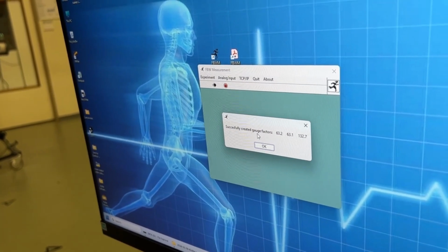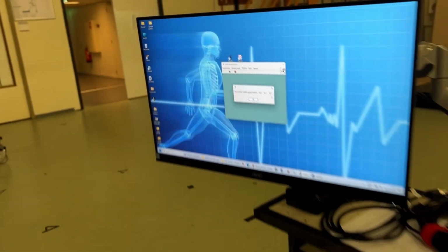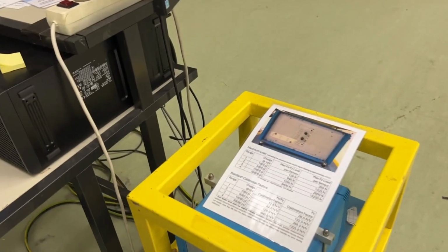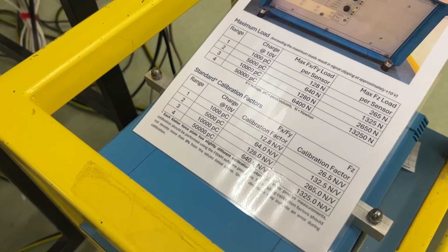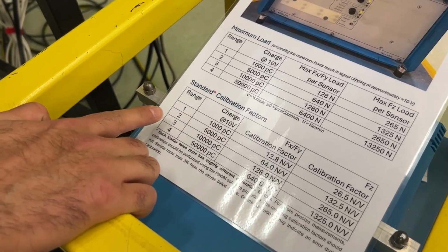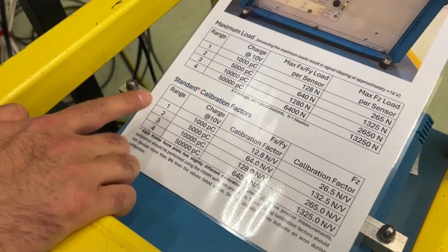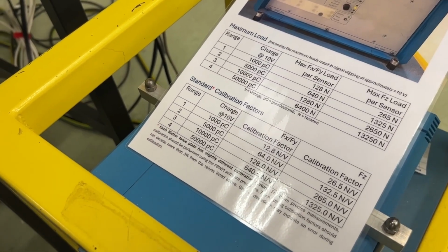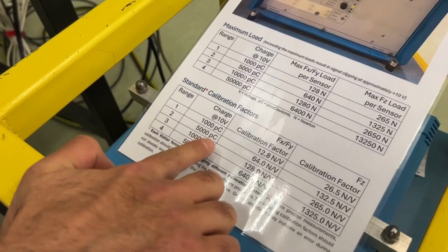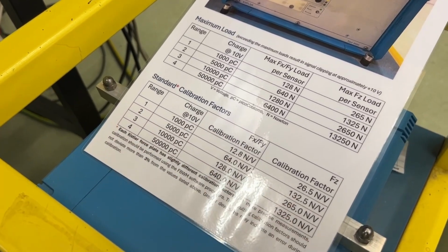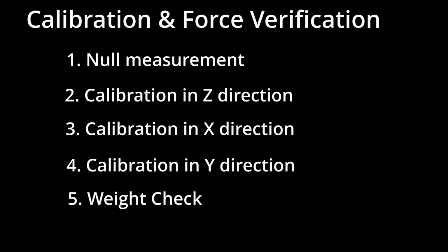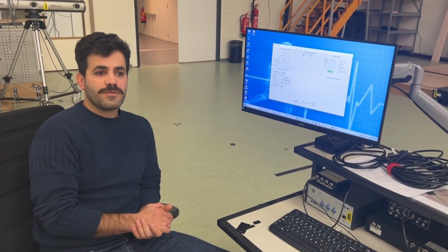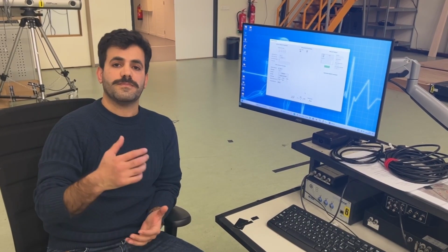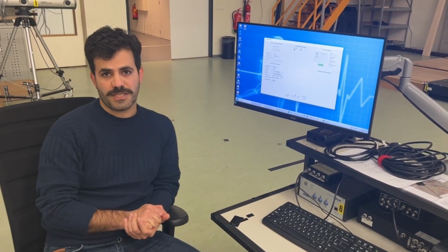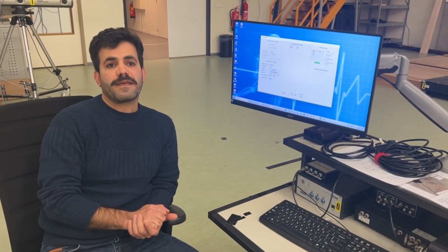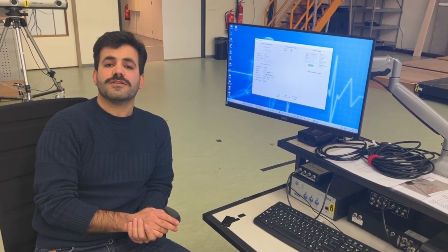Here are our gauge factors, and these numbers shouldn't deviate more than 3% of our standard calibration factors. In this case, since we have used the second amplifier sensitivity, the number should be compared with the second range. Now to verify our calibration, we want to do the very simple measurement. I'm gonna put the 25 kilograms on the force plate and check the data. So we know that the 25 kilograms is equal to 245 Newton.